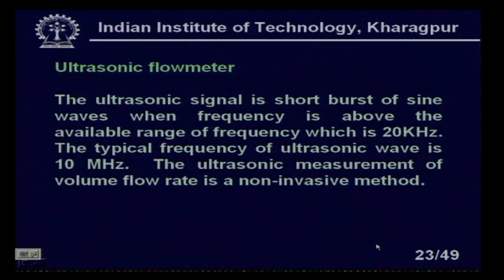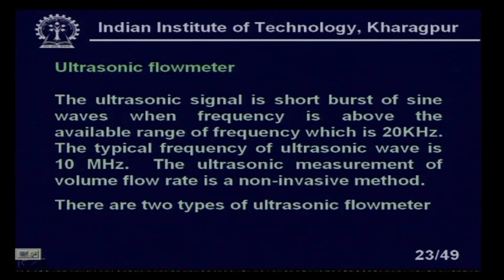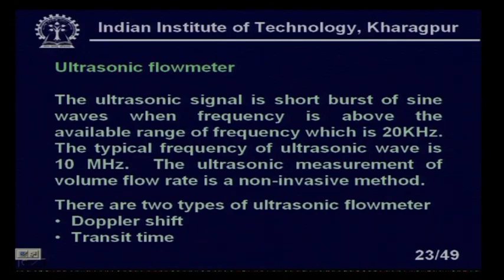The next non-invasive type flow meter we will discuss is the ultrasonic flow meter. The ultrasonic signal is a short burst of sine waves at a frequency above 20 kHz — the non-audible range — typically around 10 MHz, but ranging from 0.5 to 10 MHz. The ultrasonic measurement of volume flow rate is a non-invasive method. There are two types: Doppler shift flow meters and transit time measurement flow meters.